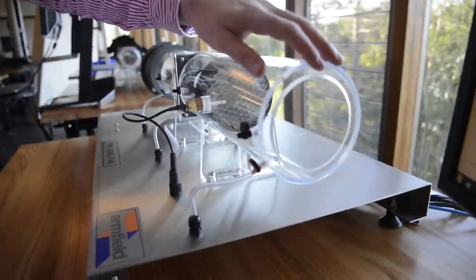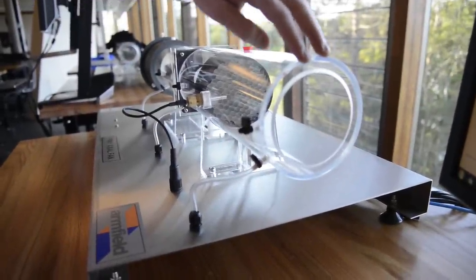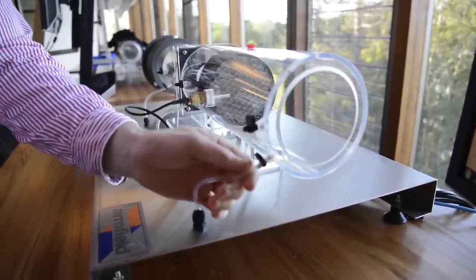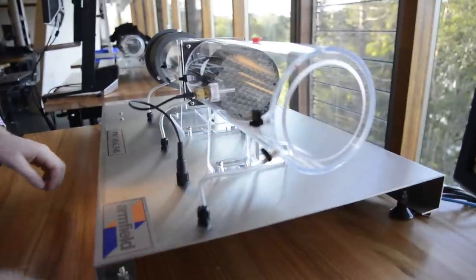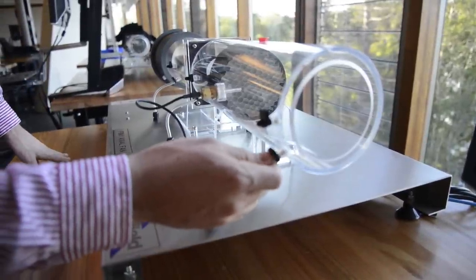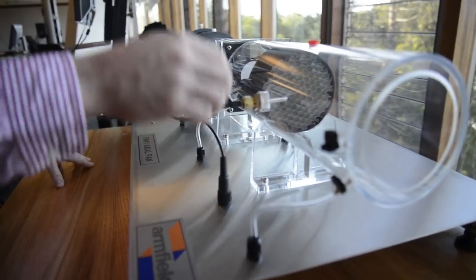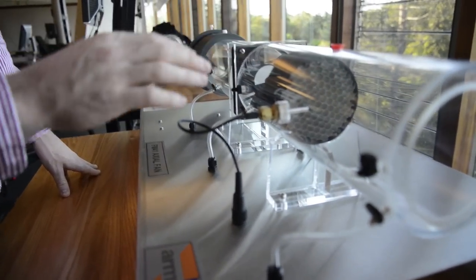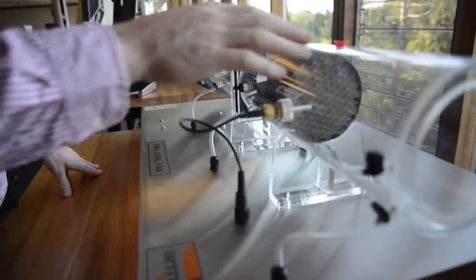To start off, we'll discuss the experimental setup. This is the orifice plate and is used at the inlet of the duct. This is the pressure sensor, which is used with the atmospheric pressure to measure the flow rate at the inlet of the duct. This is the thermocouple, which senses the temperature of air inside the duct and is used to calculate the density of the air.